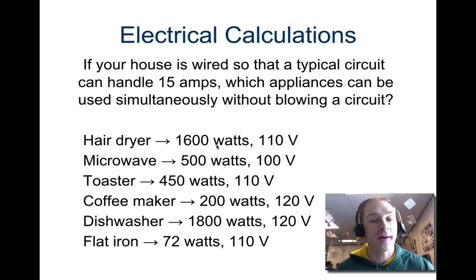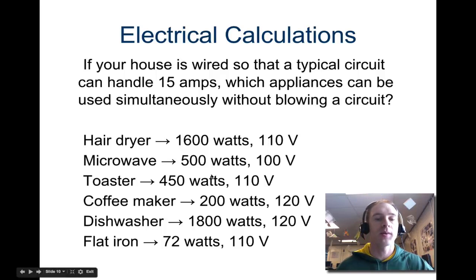Now that you've seen the magic triangle, you can solve for current really easy. Just cover up the I, and you find out it's power divided by voltage. So 1,600 divided by 110, and so on. Each one takes a certain amount of current. If all of them together take more than 15 amps, you can't run them all together.